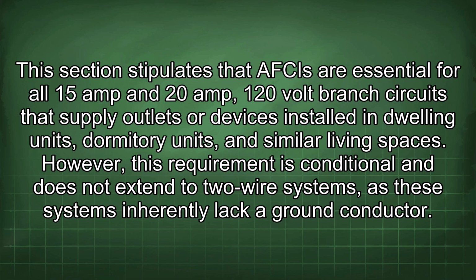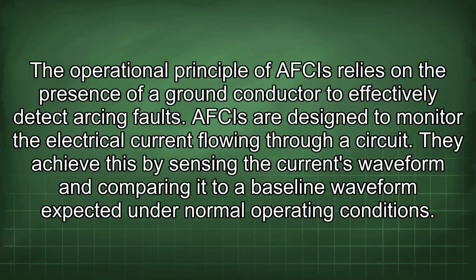However, this requirement is conditional and does not extend to two-wire systems, as these systems inherently lack a ground conductor. The operational principle of AFCIs relies on the presence of a ground conductor to effectively detect arcing faults. AFCIs are designed to monitor the electrical current flowing through a circuit. They achieve this by sensing the current's waveform and comparing it to a baseline waveform expected under normal operating conditions.